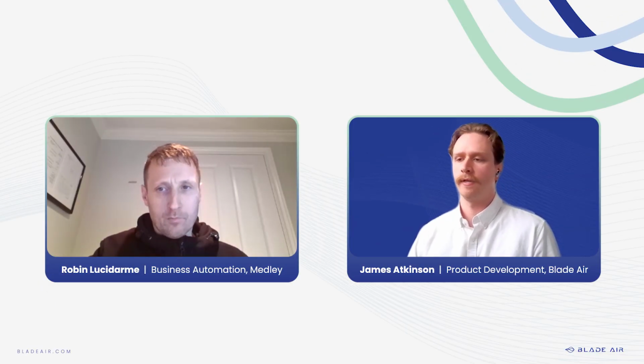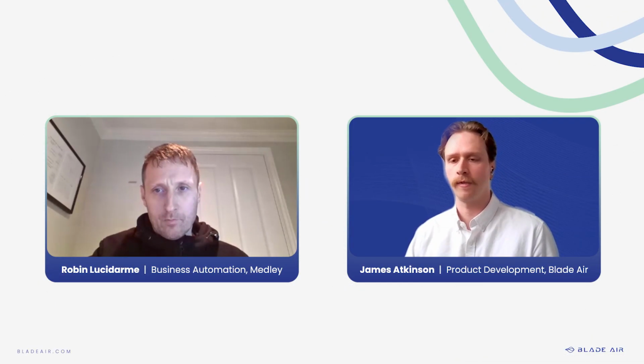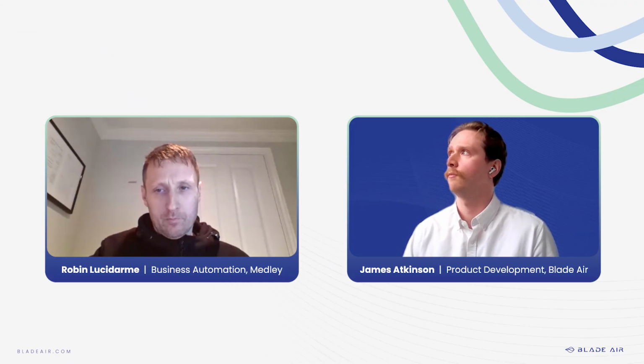Can you talk about wildfire smoke and what control sequences are typical when implementing the Pro filter? Great question. So we've had an independent study running our filters head-to-head with a MERV 13 in a wildfire event. I think it was in North Carolina. It was a couple of years ago when the wildfire smoke from Ontario, Manitoba was coming down south and reaching the States. And we had very good feedback, right? So we actually didn't have to change the operation schedules. A lot of places will actually shut down, right? They have the fire dampers, they will shut down the outdoor air. We were actually able to keep drawing fresh air and still operate quite well and not have to change the filters weekly, right?